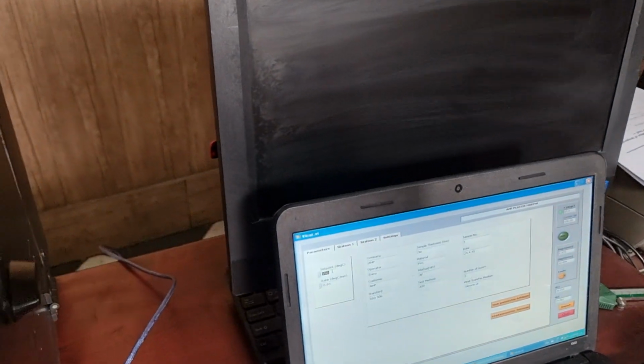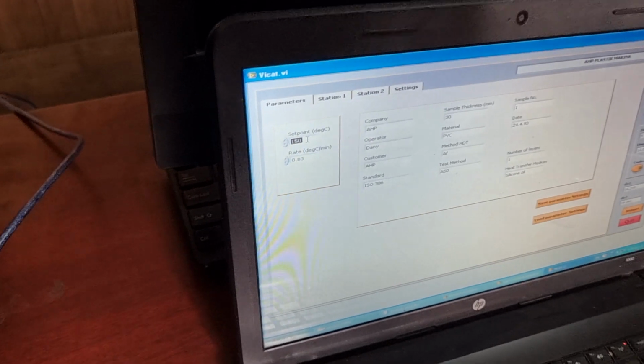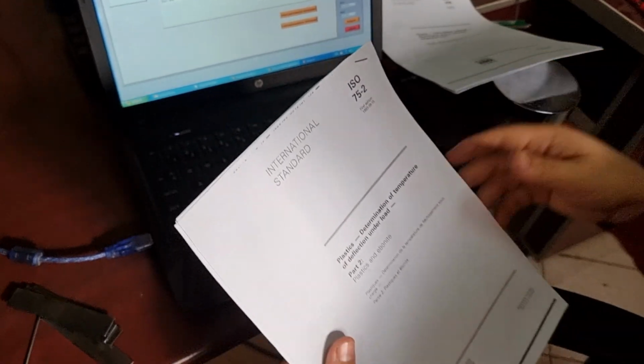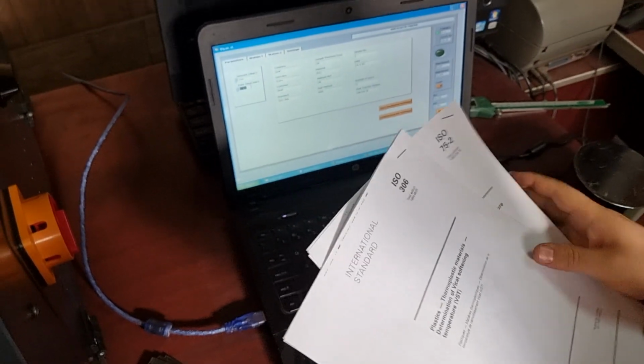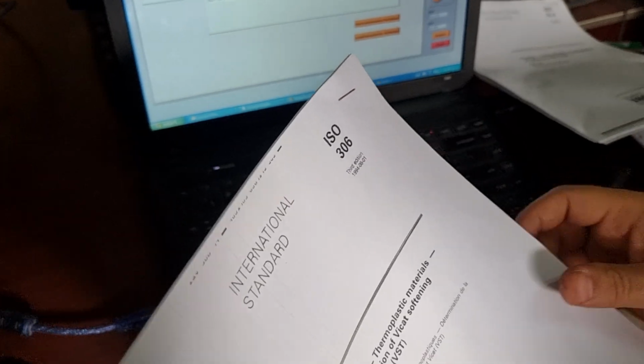Set the set point temperature to a value higher than the Vicat softening point of the material we're going to test. For example, if it's 100, you can set the temperature to 120 or 130. Now it's 150. The rate is defined in the standards here. For example, ISO 75 is for plastics, heat deflection temperature determination. Vicat is here. This is heat deflection. Vicat is ISO 306.